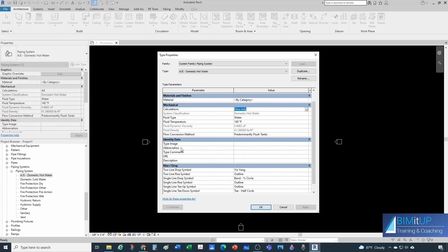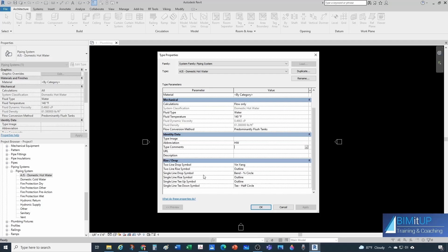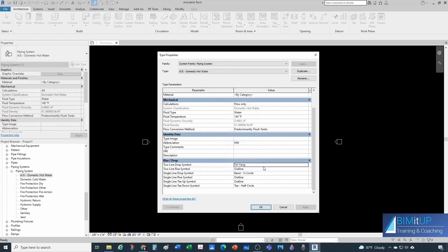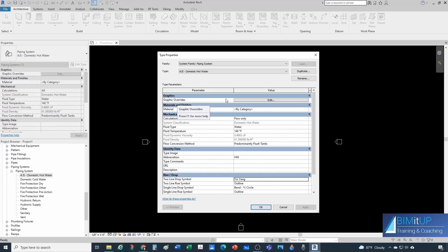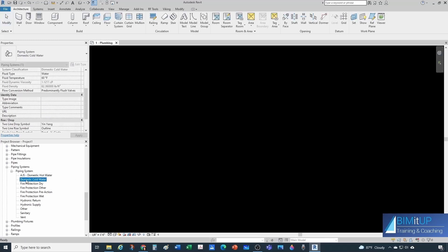You can specify a type image, and very importantly, the abbreviation. For domestic hot water, let's use 'HW' — this determines how your tags look when you tag a pipe under this system. You'll also find graphic options: how your rise/drop symbols look — either yin-yang, outline, or filled, depending on your company standards. Finally, graphic overrides let you set line pattern (solid, dashed, dotted) and color. It makes sense to keep it red for domestic hot water.